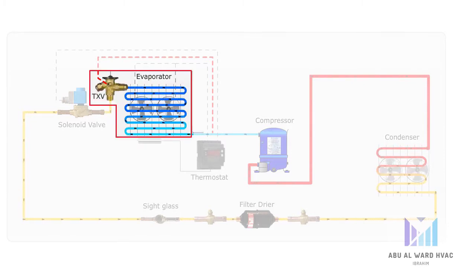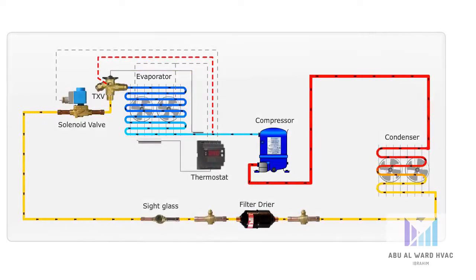They do this by controlling the refrigerant superheat at the evaporator outlet. As a consequence, these valves are especially suitable for liquid injection in so-called dry evaporators. The superheat of the evaporator outlet is proportional to the evaporator load. Certain TXV versions can also be used to reduce superheat in systems with capacity regulation performed by hot gas bypass valves.